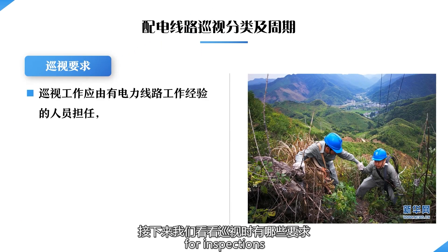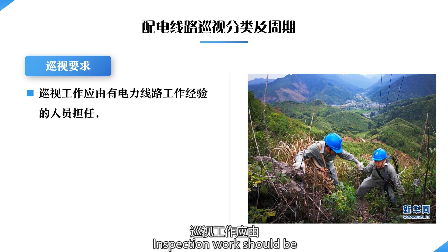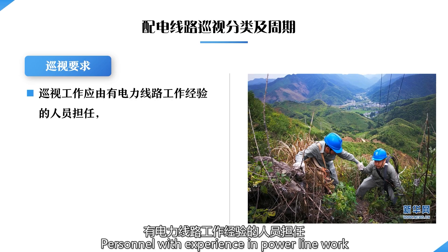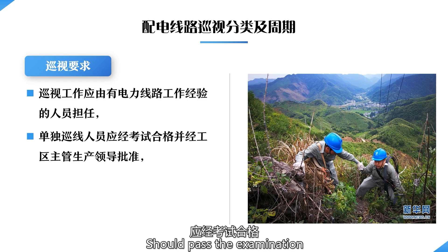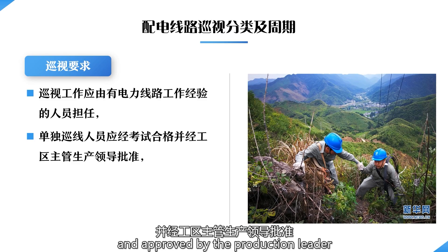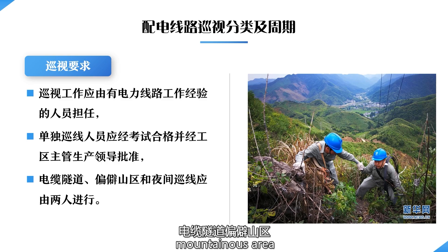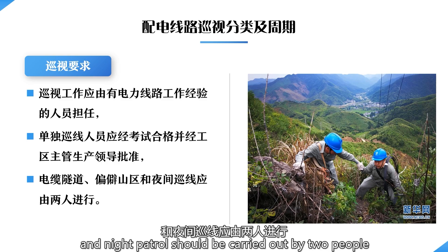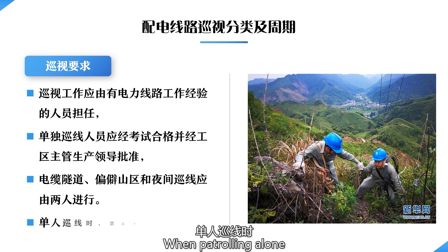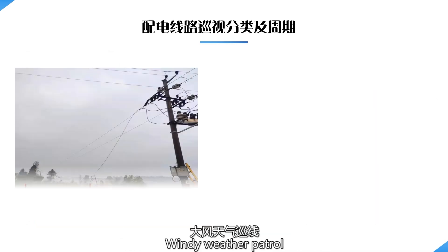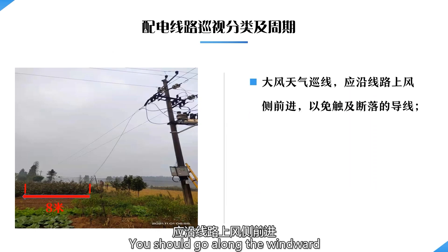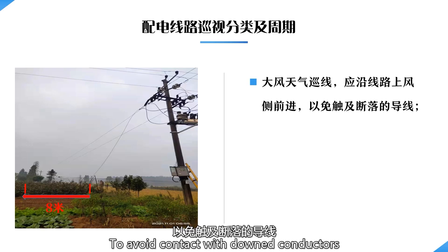Inspection work should be performed by personnel with experience in power line work. Individual inspectors should pass the examination and be approved by the production leader in charge. Cable tunnel, remote mountainous area, and night patrol should be carried out by two people. When patrolling alone, climbing poles and towers is prohibited. During windy weather patrol, you should go along the windward side of the line to avoid contact with downed conductors.